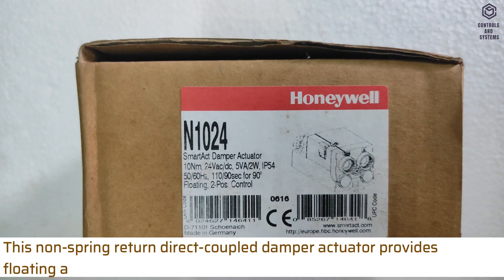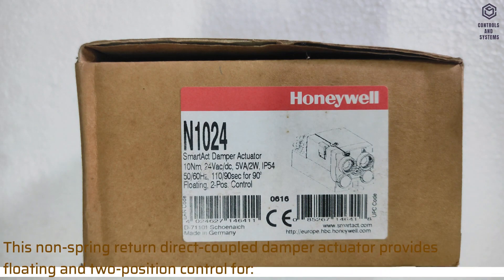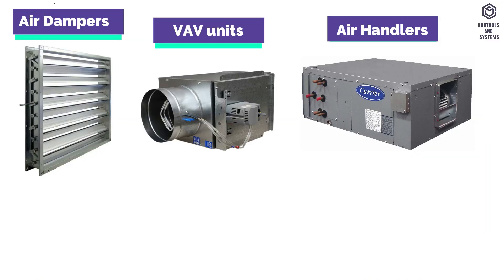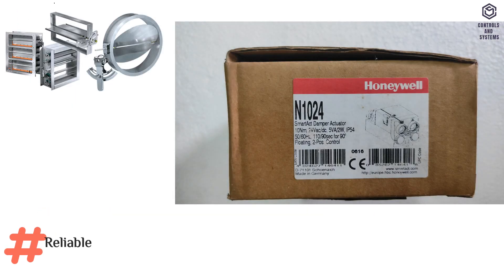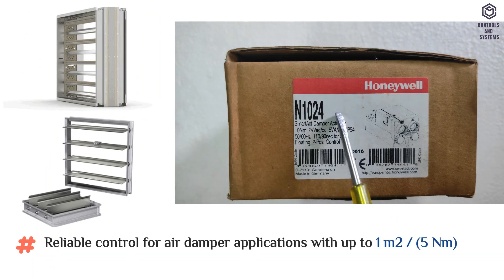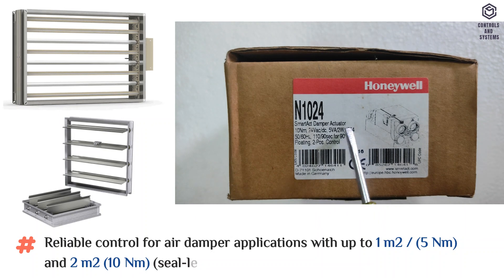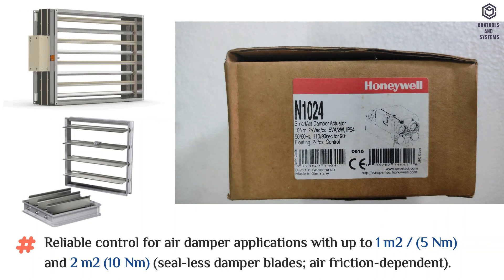Device Overview: This Non-Spring Return Direct Coupled Damper Actuator provides floating and two-position control for air dampers, VAV units, air handlers, ventilation flaps, and louvers. It provides reliable control for air damper applications with up to one square meter for 5Nm, and two square meters for 10Nm seal-less damper blades.